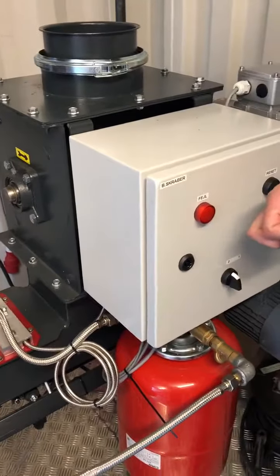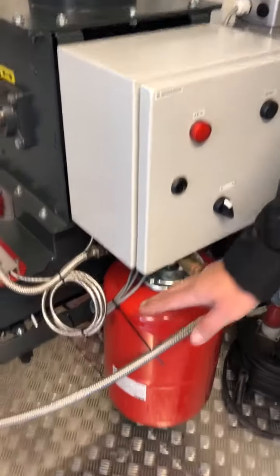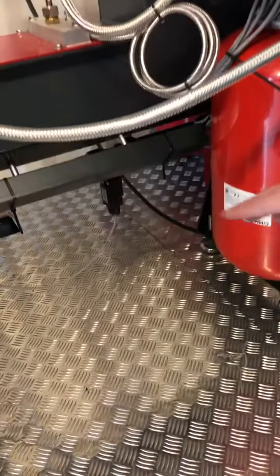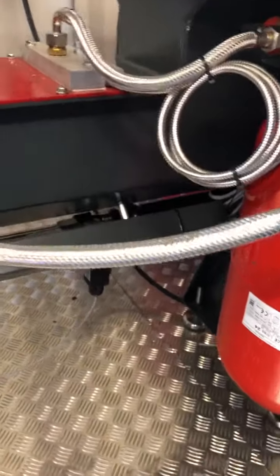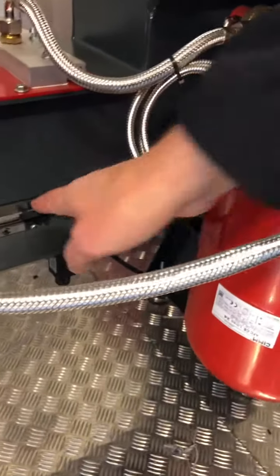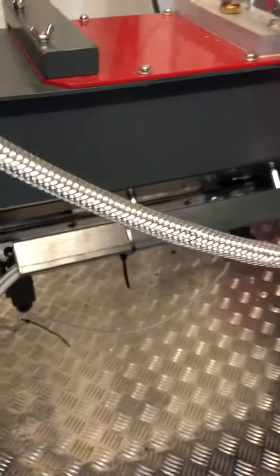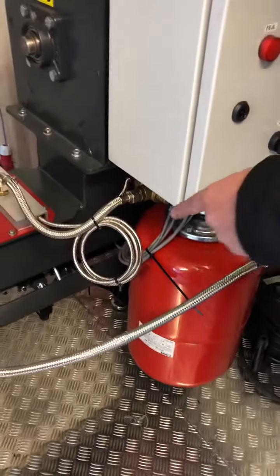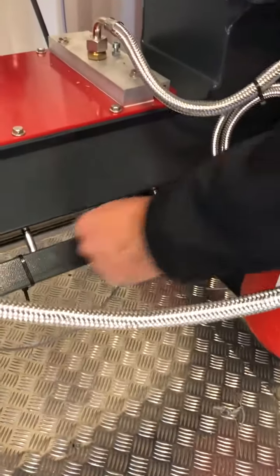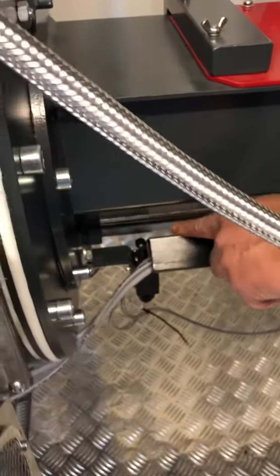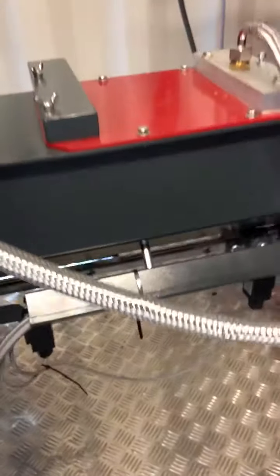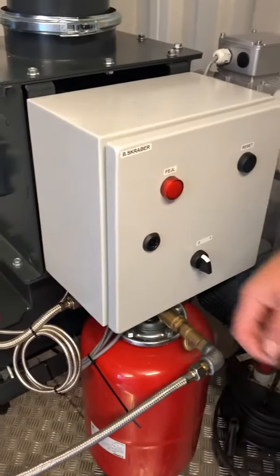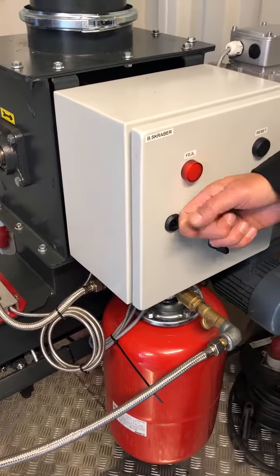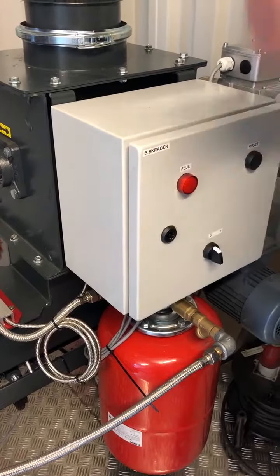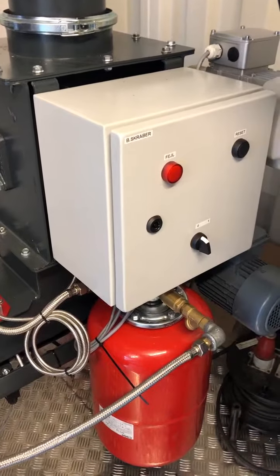This is the control panel, the control box for the ash scraper in the bottom of the burner tube. And this is that actuator placed here under the auger channel, and it will work from the one sensor to the front sensor, stop again and turn and go back again. And it goes very slowly. Inside the box there is a small PLC where you can adjust the time between the sensor works, or the scraper.